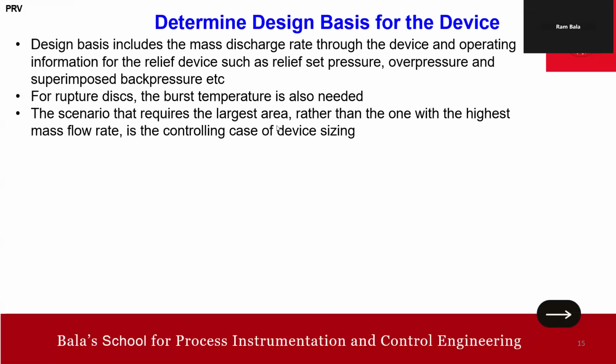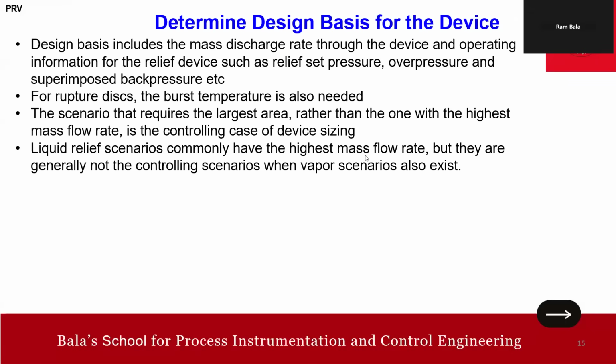The scenario that requires the largest area, rather than the one with the highest mass flow rate, is the controlling case for device sizing.